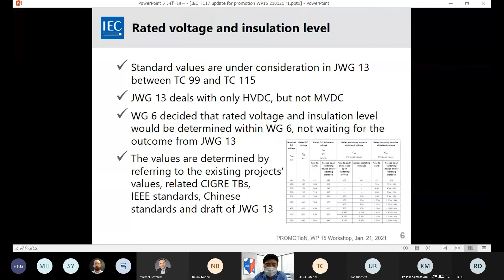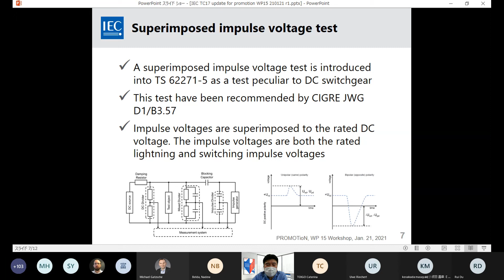Next is superimposed impulse voltage test. It is introduced into the new technical specification. As you well know, this test has been recommended by CIGRE joint working group between D1 and B3. And in this test, impulse voltage is superimposed on the rated DC voltage. The impulse voltages are both the rated lightning impulse and the switching impulse voltage.